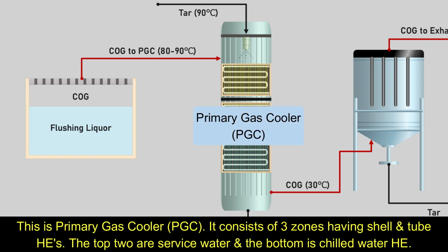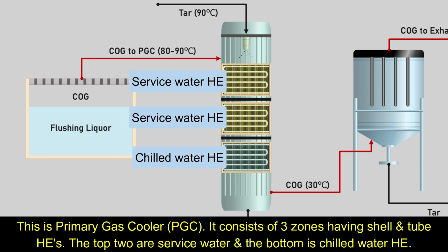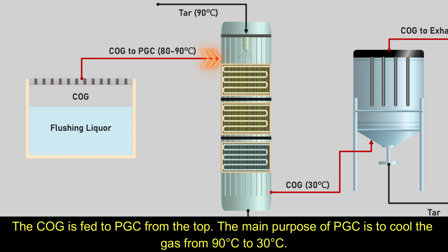This is primary gas cooler. It consists of 3 zones having shell and tube heat exchangers. The top 2 are service water and the bottom is chilled water heat exchanger. The coke oven gas is fed to primary gas cooler from the top. The main purpose of primary gas cooler is to cool the gas from 90 degrees centigrade to 30 degrees centigrade.